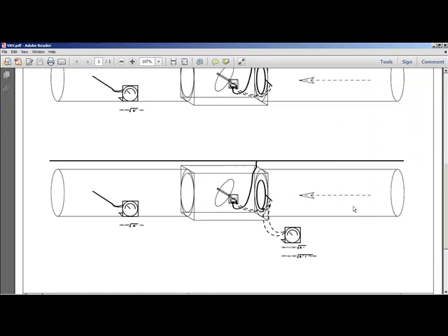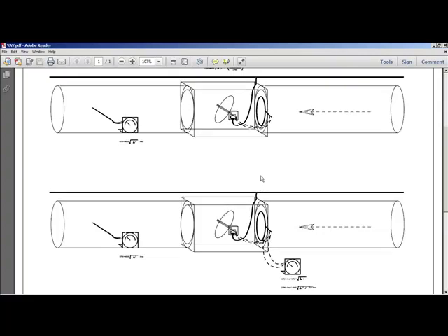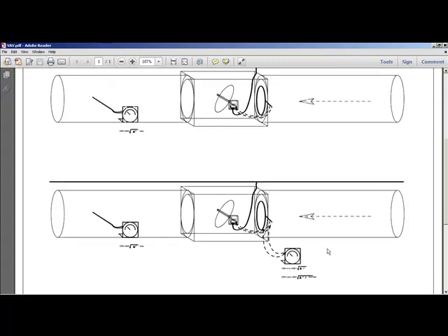Now again, if we're just measuring a straight duct, it's 4005 times the square root of the velocity pressure times the area. When we're dealing with the VAV box, we have a K factor that we have to deal with. The best equation is to say your CFM is equal to your known K factor in CFM multiplied by the square root of the differential pressure.